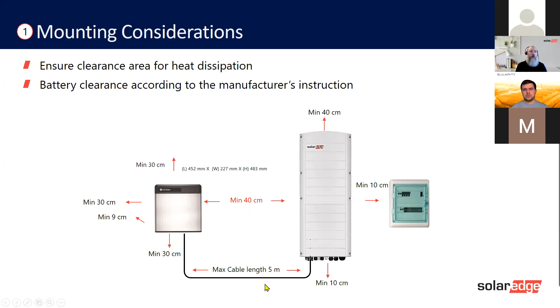Distance between the battery and the inverter is a minimum of 40 centimeters, but you must have a cable of 5 meters here. That's the most you can have. So maximum cable length is 5 meters. This is the longest on the DC side, okay? DC side.